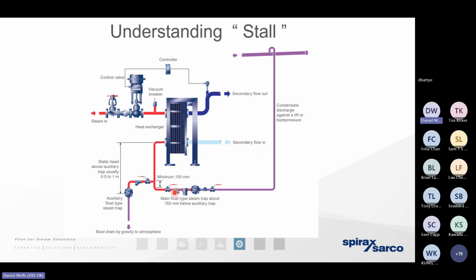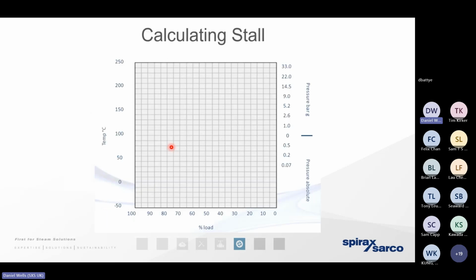Unfortunately, we're going to need a pressure drop across that steam trap in order for it to work efficiently. So in certain applications, especially those working on relatively low pressure, low flow, it may mean that we've no longer got enough motive pressure within the heat exchanger itself to push the condensate across the steam trap. For example, if we're condensing steam at 0 bar gauge, 100 degrees, and we've got a back pressure in the condensate infrastructure, it may well be that we don't have enough pressure in the heat exchanger to push the condensate away. The condensate is going to back up, it's going to flood the pipework, and we're no longer getting the heat exchange that we are hoping for or expecting.